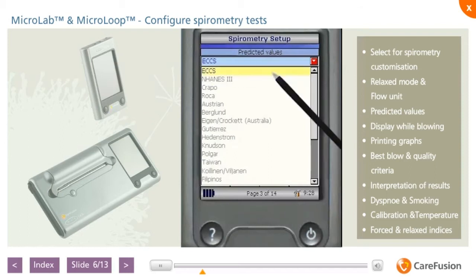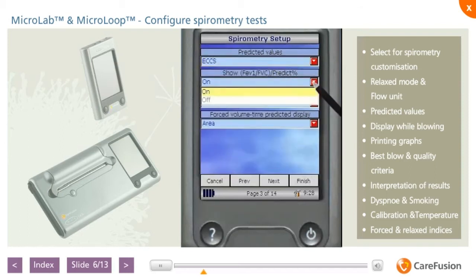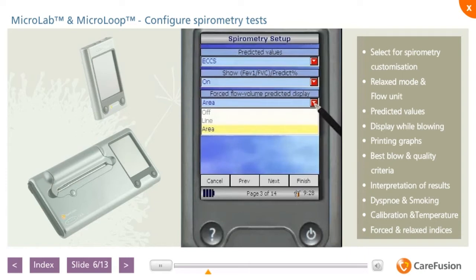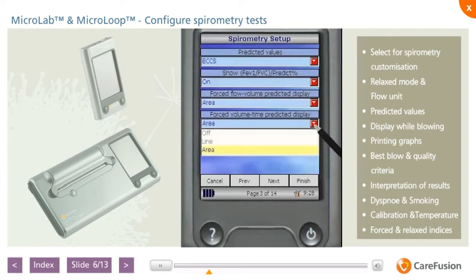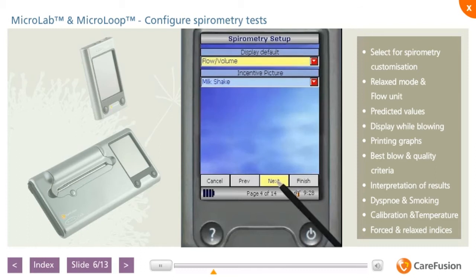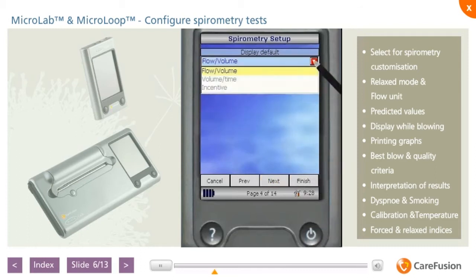You can choose to test without displaying the FEV1-FVC ratio percentage of predicted, and for this purpose deactivate the indicator. You can choose if the predicted value marker should be displayed as an area on the flow volume and volume time graph or as a dotted line. Select Next to continue. The display default allows a choice of flow volume, volume time or animation to be selected.